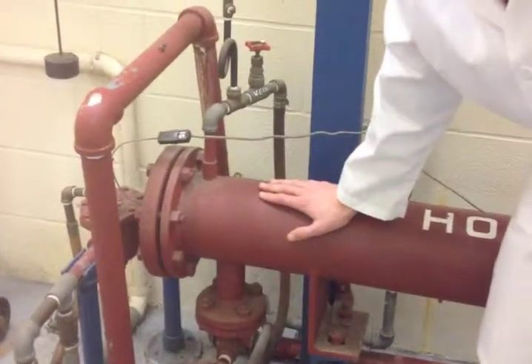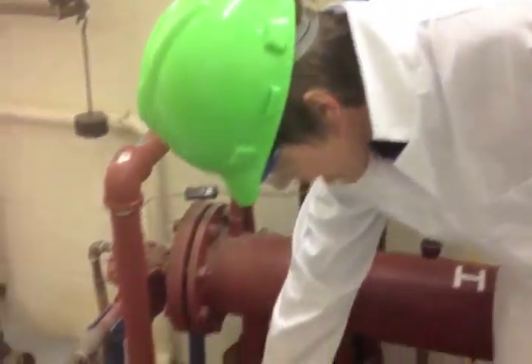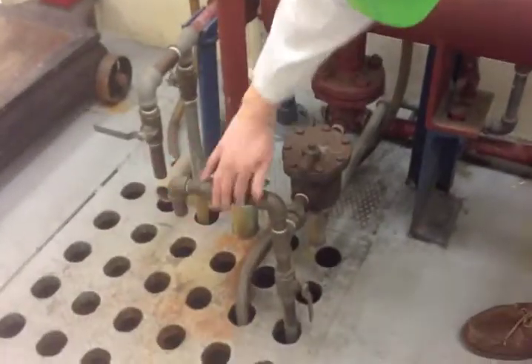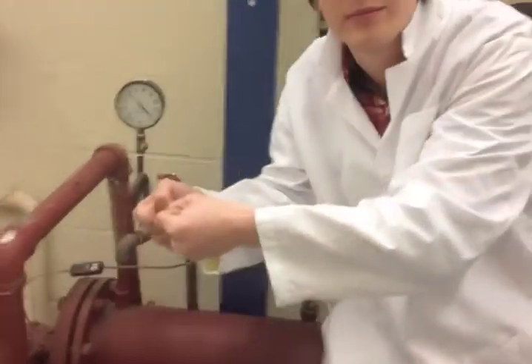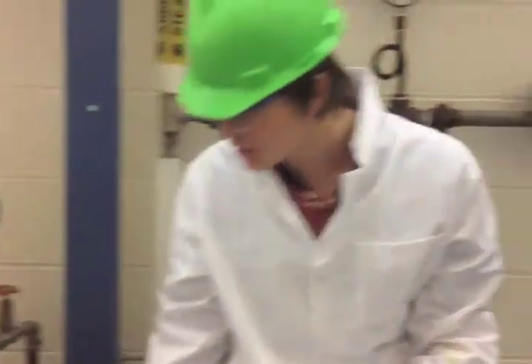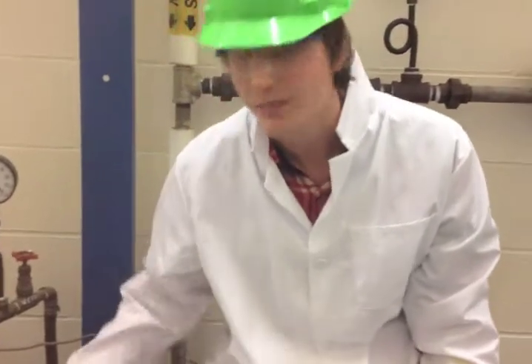When steam condenses in the shell, it comes through the steam trap and it exits out this tube here. When the steam trap's working effectively, it won't just flow, but instead you'll get a whoosh, whoosh. And that's what they're designed to do, because the idea is we want to trap the steam inside the shell while letting out the condensate in short bursts to maintain that pressure. So we can put a bucket down there, measure the amount of condensate, and use that mass to determine the amount of heat lost by the steam. Next, let's move to the double pipe heat exchanger.